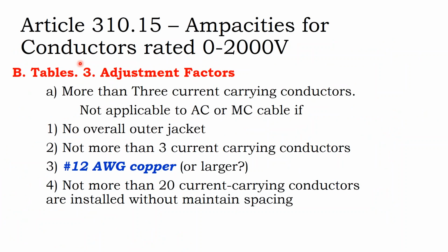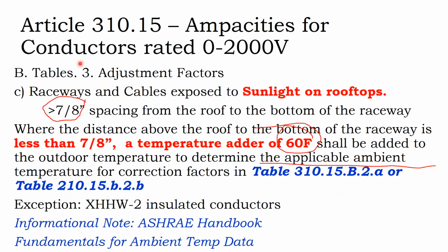So, more than 3 conductors in a raceway, exposure to sunlight on the rooftop. Then there's an exception listed. It says if you're using XHHW-2 insulated conductors, this rule may not apply. And so that gets into, okay, we have a couple of different rooftop conductors here. We have USE-2, we have PV wire, we have THW-2, we have XHHW-2. It might be that if we specify a more expensive conductor that is less subject to burning up when it gets into these hotter temperatures, we might be able to get around the temperature correction factor by spending a little bit more on our cable.